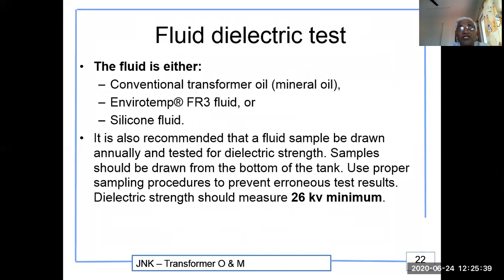Fluid dielectric test. The fluid is either conventional transformer oil, what we call mineral oil, or environmental fluid, or silicone fluid, or any other fluid also, as new ones are coming. It is also recommended that a fluid sample be drawn annually and tested for the dielectric strength of the oil. Samples should be drawn from the bottom of the tank. Use proper sampling procedure to prevent erroneous test results. Dielectric strength should measure minimum 26 kV, but maximum can be about 50 kV per 11 kV application.